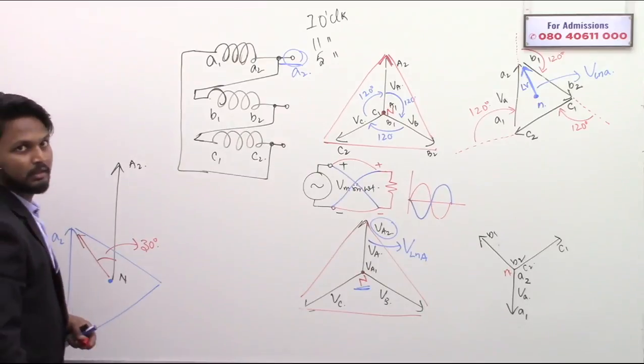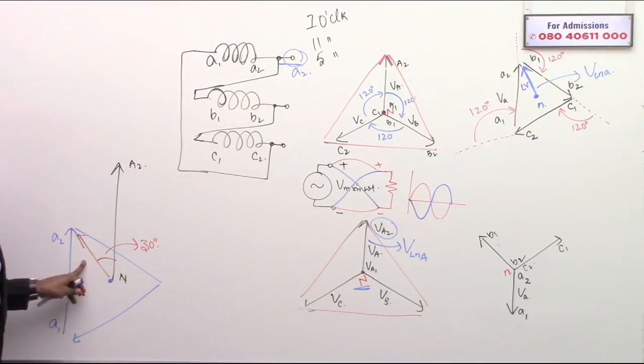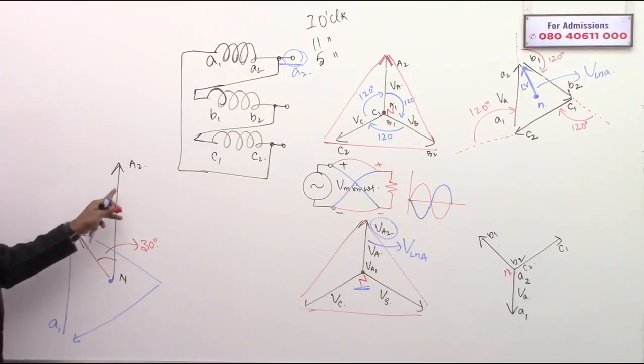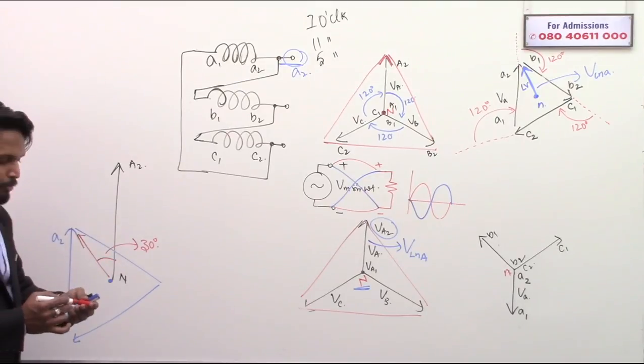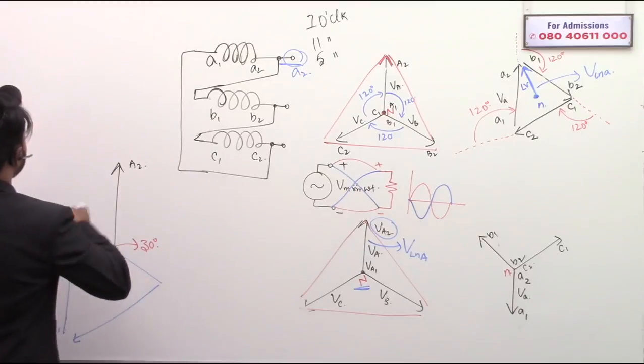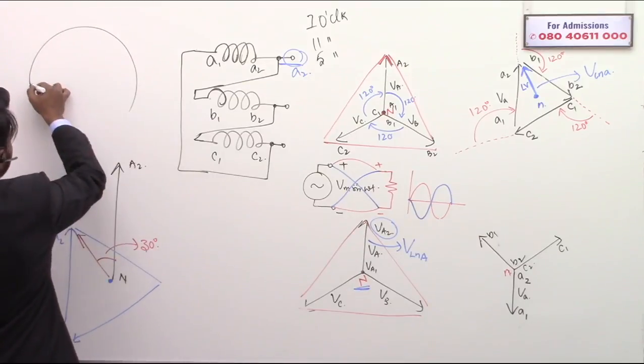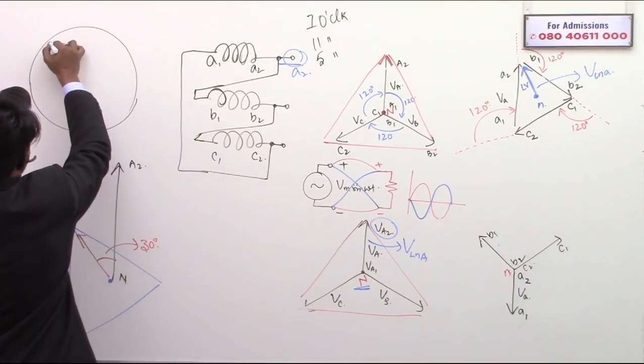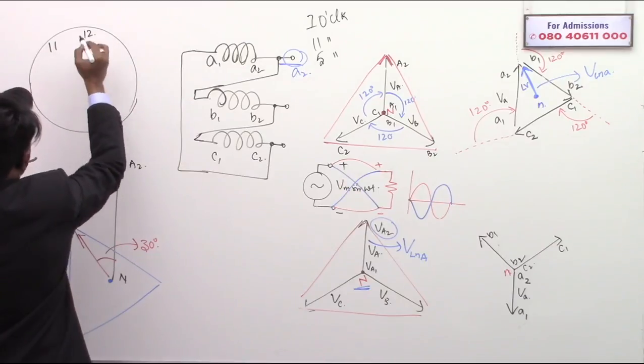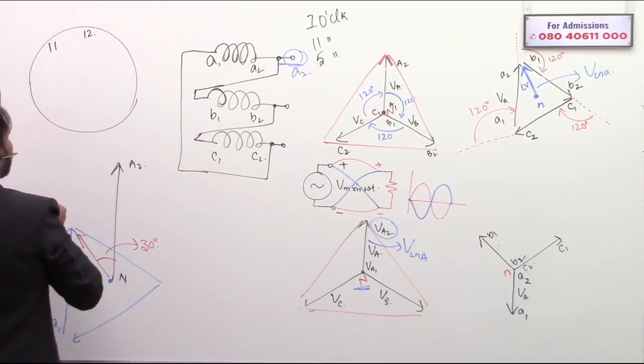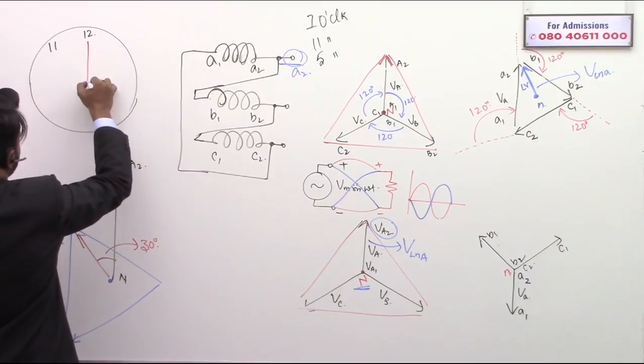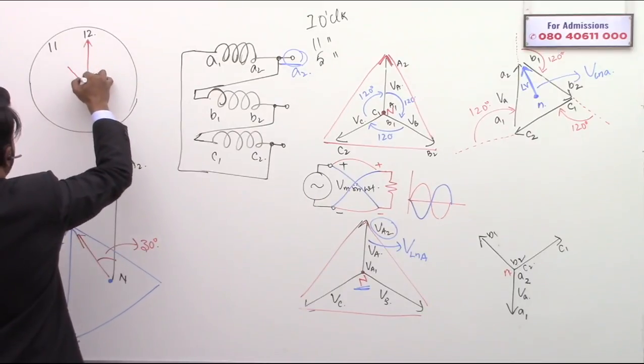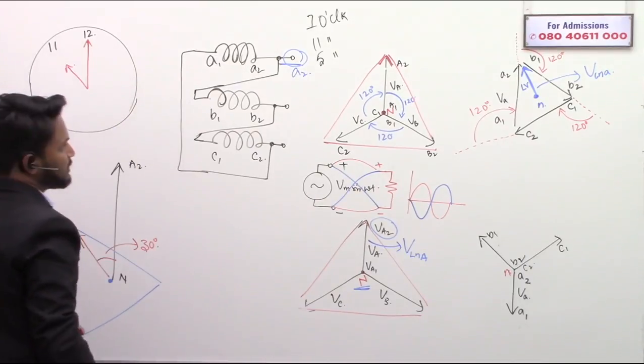So there is 30 degrees of phase difference between both of them. The LV side line to neutral phasor is at 11 o'clock position, and HV side line to neutral phasor is at 12 o'clock position. Tell me, what is the phasor group? HV is this and LV is this.